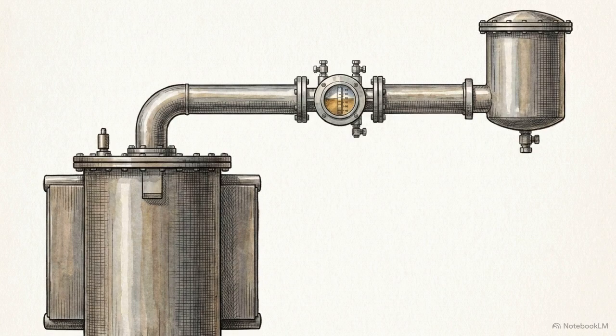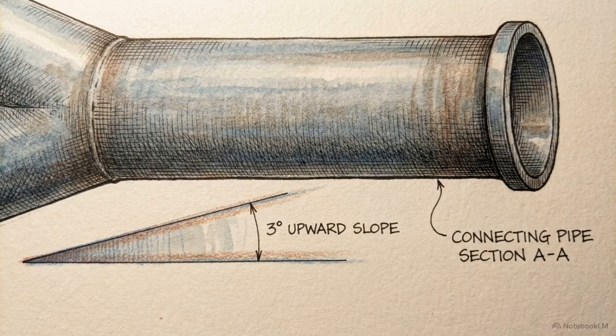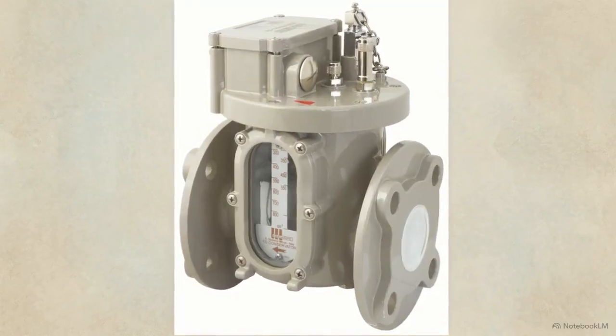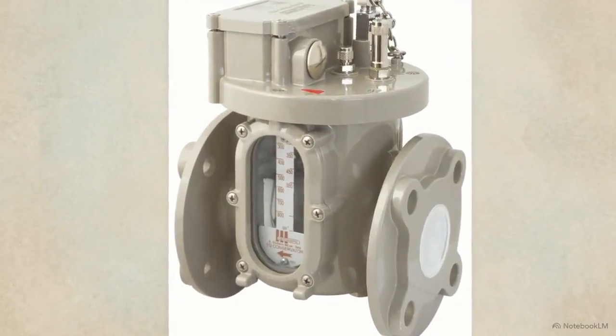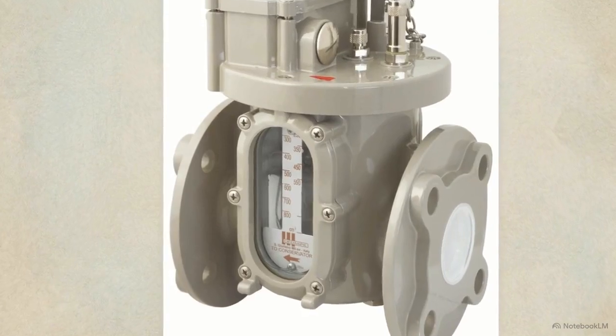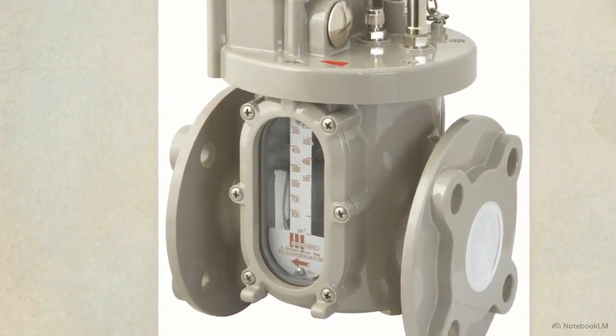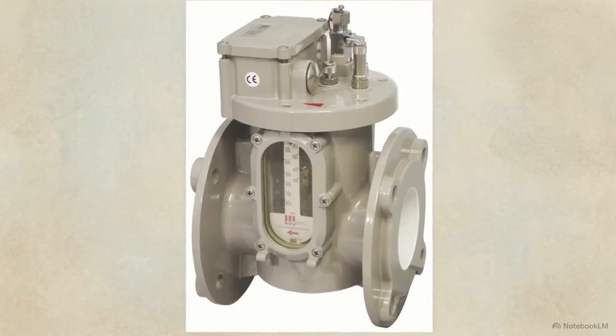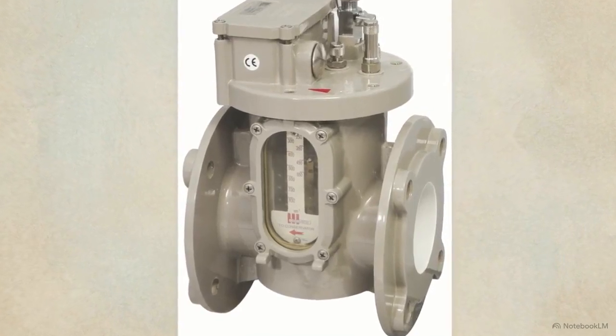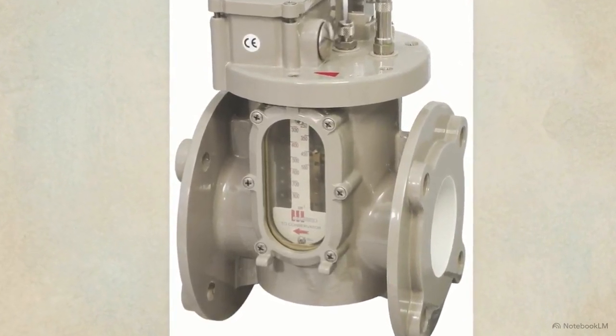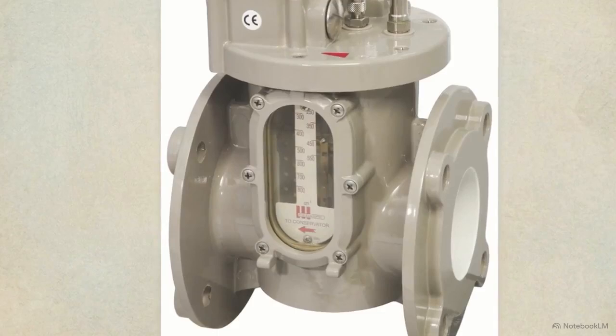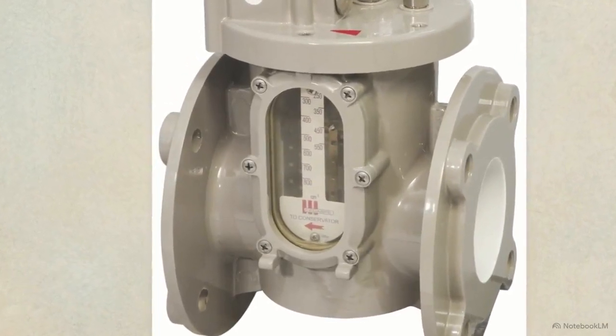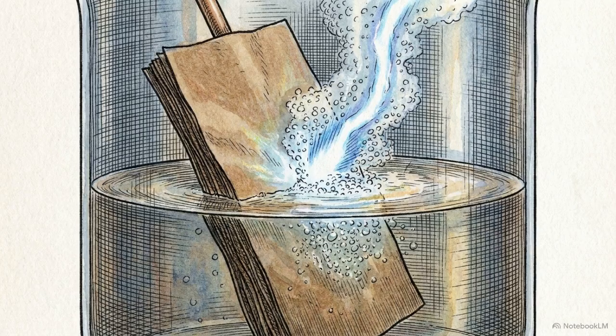Its placement is highly specific. It must sit exactly on the pipe connecting the main oil tank to the expansion conservator, pitched upward at an angle between 2 and 5 degrees. The relay is built for harsh environments, utilizing a heavy-duty cast aluminum body with dual mounting flanges to integrate directly into the oil flow path. The front features a calibrated inspection window. The vertical graduated scale etched onto the glass is designed to measure the exact cubic volume of gas accumulating inside the chamber. The relay operates on a simple physical law.